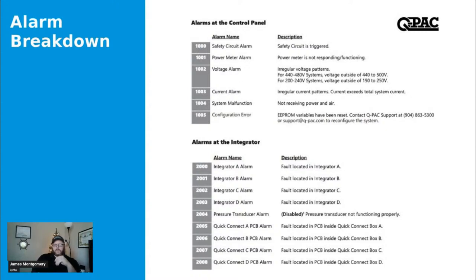2005 through 2008 are for the respective PCBs that we were just talking about. So typically when you get a 2005 to 2008, you've got an issue inside that PCB, whether that be wiring or an issue with the device itself. So these alarms, 2000 all the way through 2008 minus the 2004, are pretty synonymous with each other. If you've got an individual fan offline, then you're going to see a 2000 through 2003. If you've got just a miswiring issue and the PCB just can't determine fan status at all, then you're going to have a 2005 through 2008. I think I might have said that incorrectly in the beginning, but 2000 through 2003 are individual or more fan alarms, and 5 through 8 is a miswiring application.